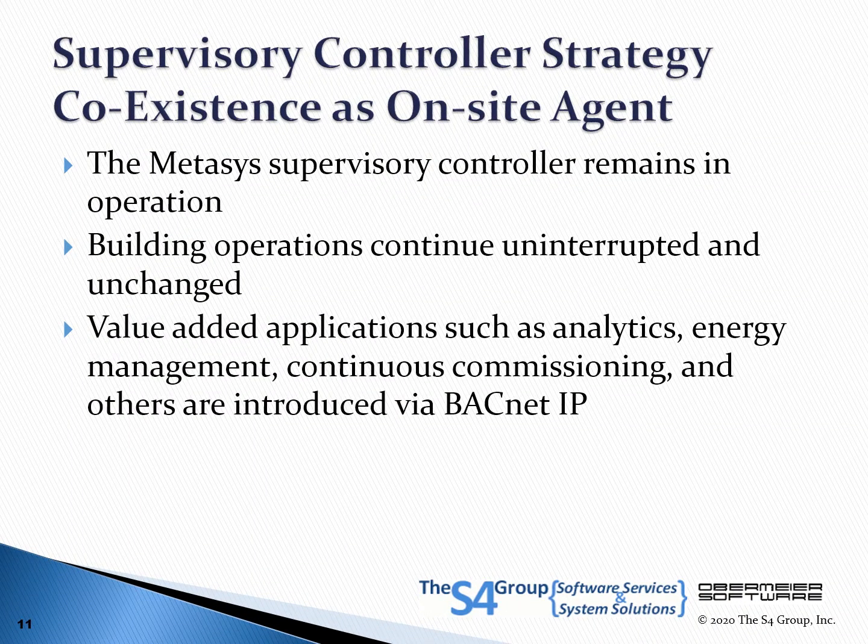BACnet-enabled value-added applications may be locally hosted or be cloud-based applications. It is business as usual from the standpoint of the Metasys Supervisory Controller, the Operator Workstation, and building operations. The BACnet application has full read, write, override, and release functionality for all N2 points.